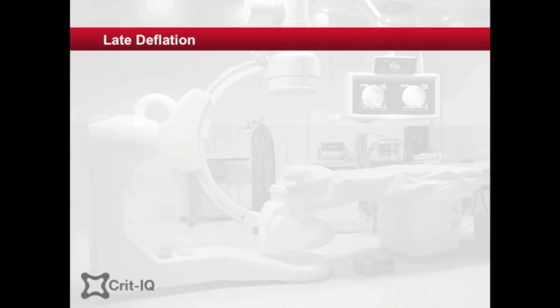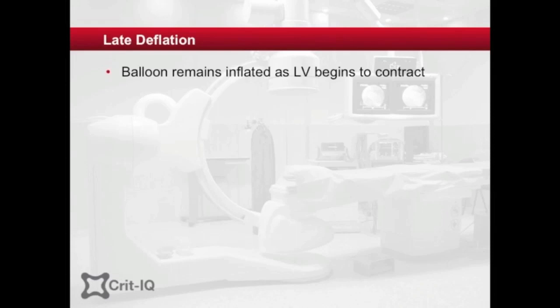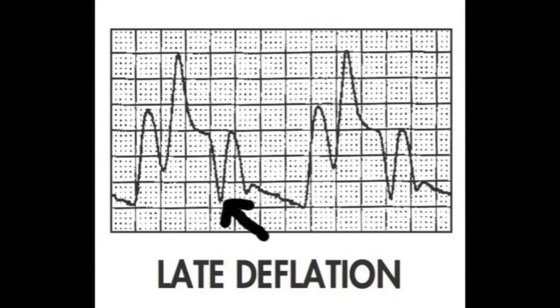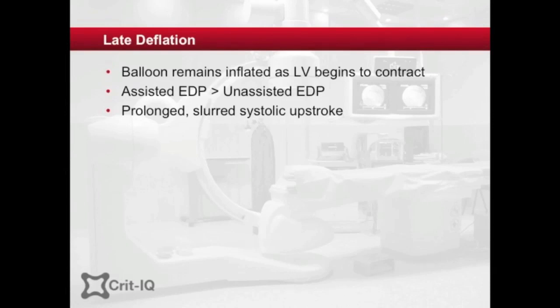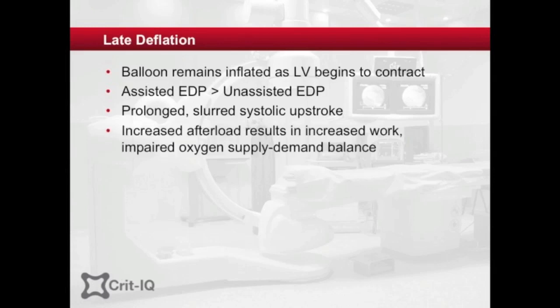Late deflation of the balloon means the balloon remains inflated after systole has begun. The pressure waveform will display an assisted aortic end diastolic pressure that is higher than the unassisted end diastolic pressure. The rate of rise of the assisted systole will be prolonged with a gentler upsloping gradient than usual, and depending on the heart rate, diastolic augmentation may appear widened as it lasts for a longer period due to the balloon remaining inflated for longer. Physiologically, afterload is increased as the left ventricle contracts against greater resistance, so myocardial oxygen demand and consumption rise.